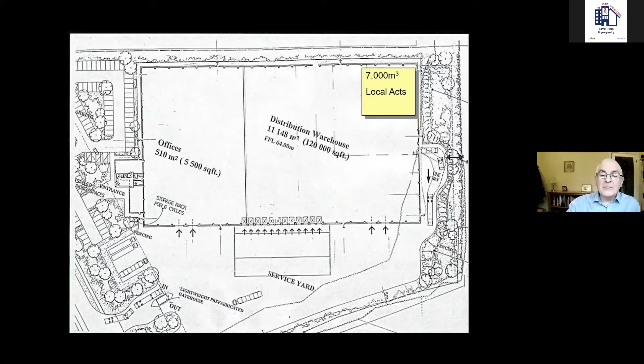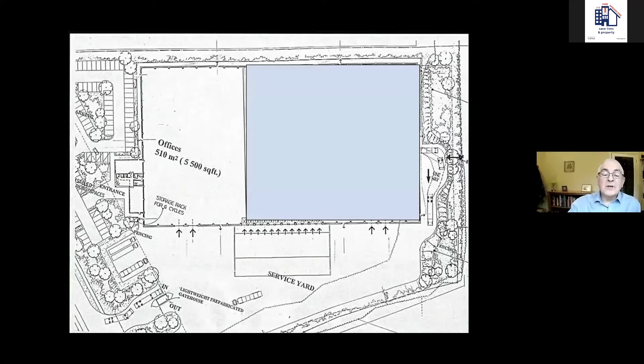Local acts were very powerful pieces of legislation, but we didn't have a local act in Northamptonshire, unfortunately. We used the Approved Document B, which at that time only said that multi-storey industrial buildings no more than 18 metres high could be built up to a maximum of 7,000 square metres without sprinklers. That 7,000 square metre limit was imposed on this plan, and the building in front of us was exceeding those standards where sprinklers would have been necessary. The owner, or rather the developers, were intent on not sprinkler protecting the building.